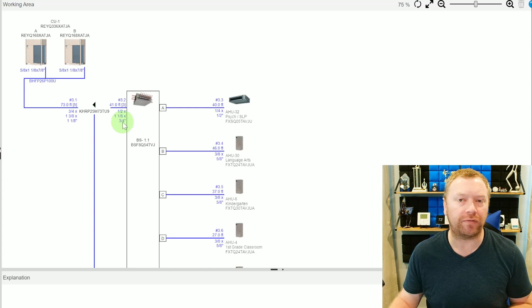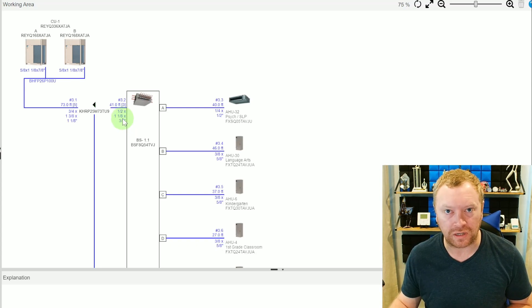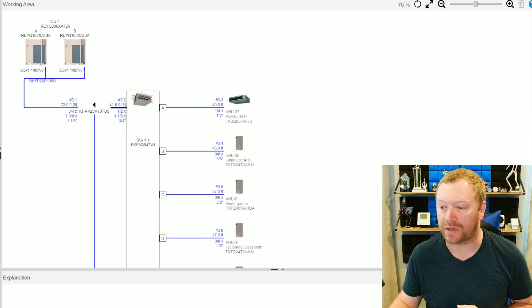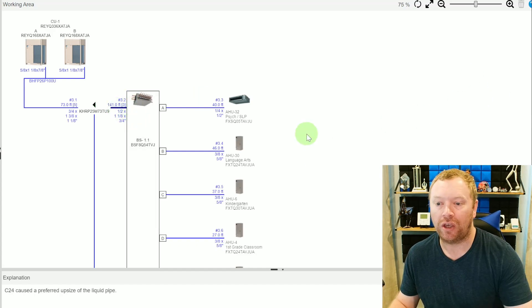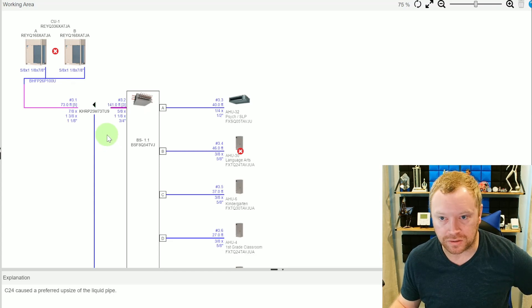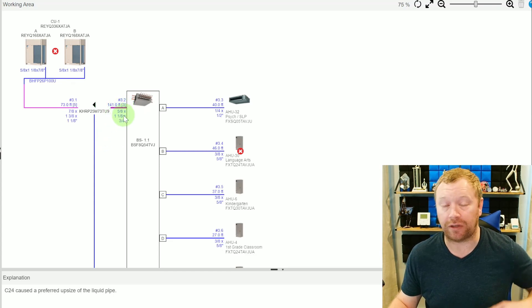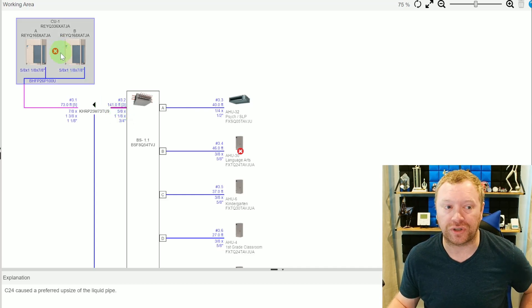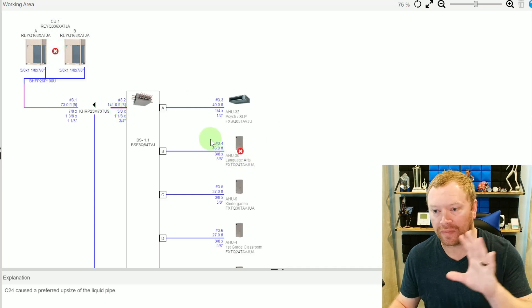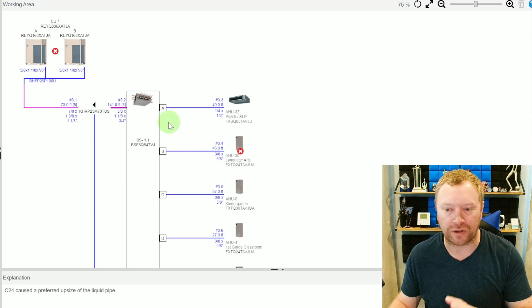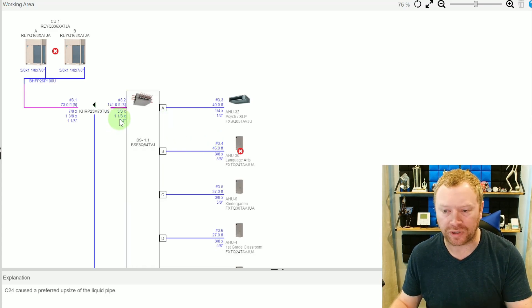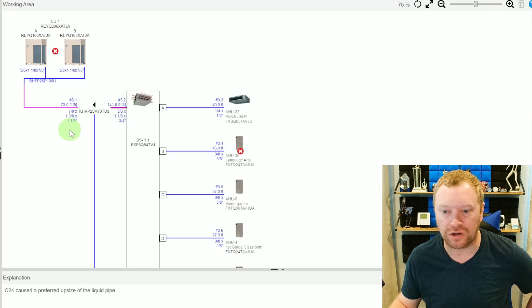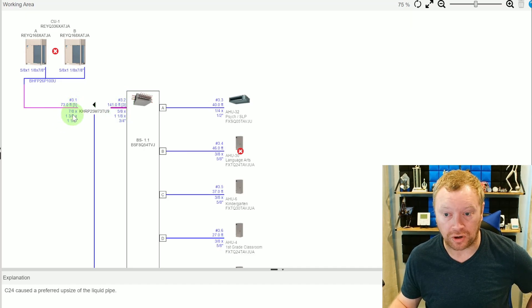Right now, these pipe sizes are automatically calculated based on capacity connected downstream. So this one-half, one-and-one-eighths, and three-quarter-inch line set is going to be sized based on the length and the capacity downstream. If, for whatever reason, this can't be 41 feet, and it needs to be, let's just say 141 feet, let me go ahead and change that real quick, you're going to notice that all of a sudden, we have a pipe size change. And in this particular example, we're breaking some rules, so you can see an X here and an X here.